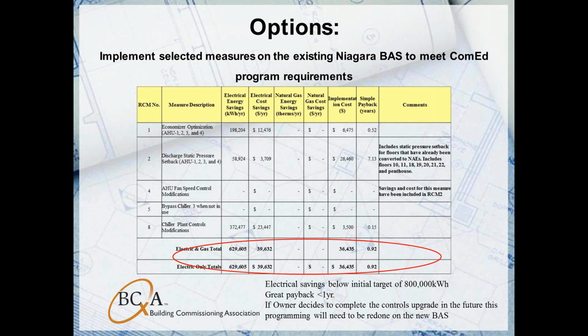So again, we did some legwork here, and we came up with some options for the owner. Option one is to keep the Niagara BAS and the Johnson BAS separate and just implement the measures that we're able to implement on the Niagara BAS and meet the minimum requirements of the retro commissioning program here. So in this case, we can implement some of these measures here. The downside is that our electrical savings is lower than our target, but we still have a pretty good payback, under a year, not too bad.